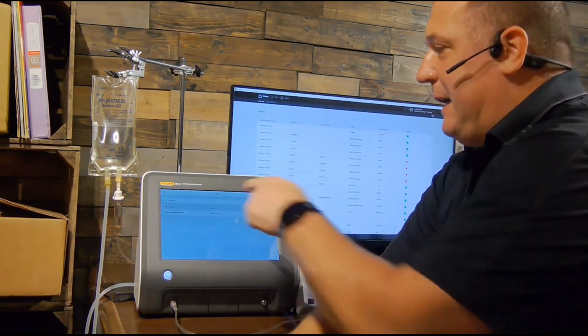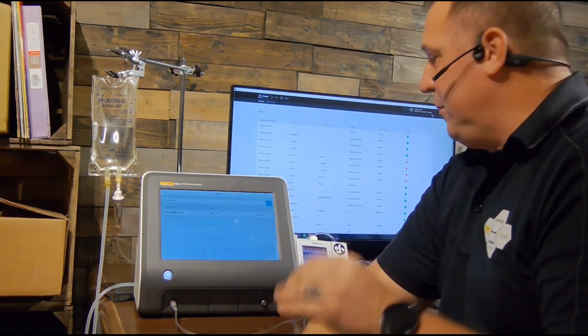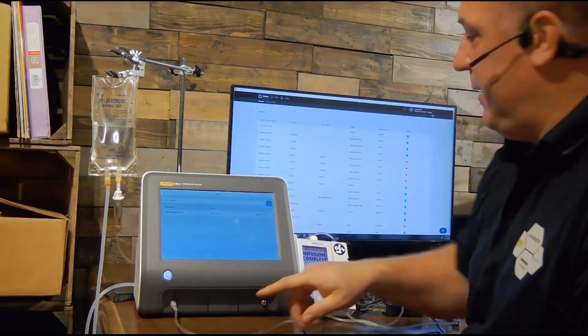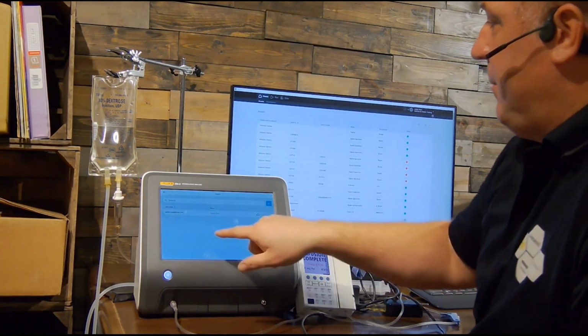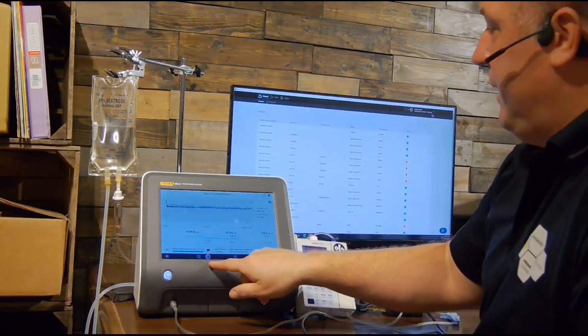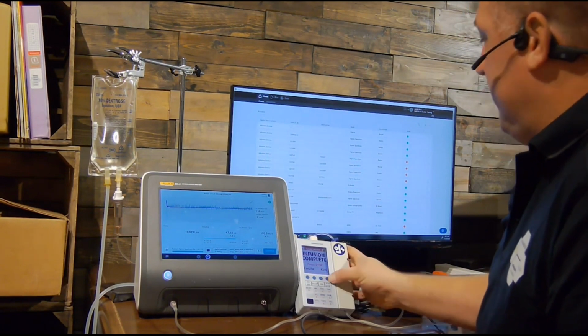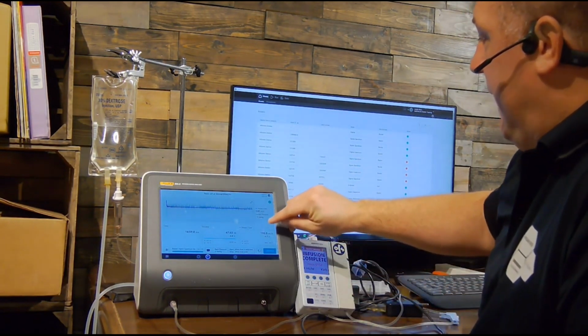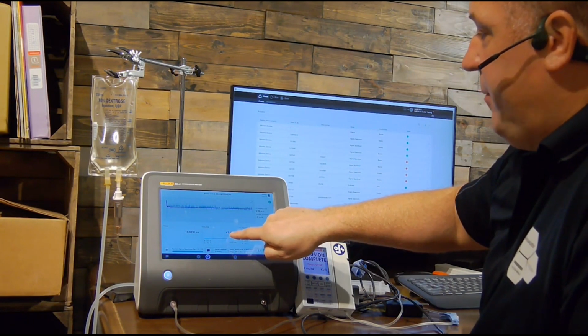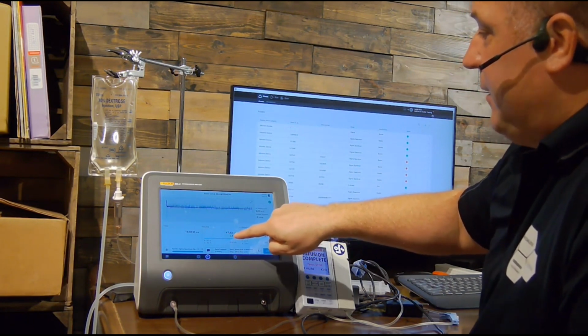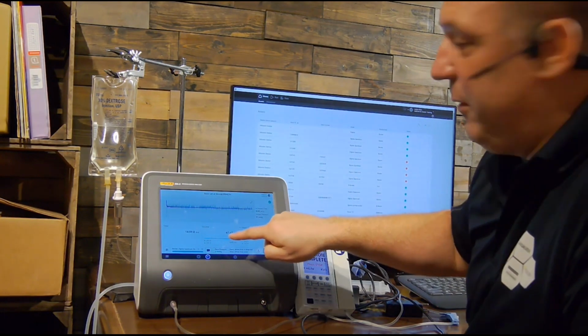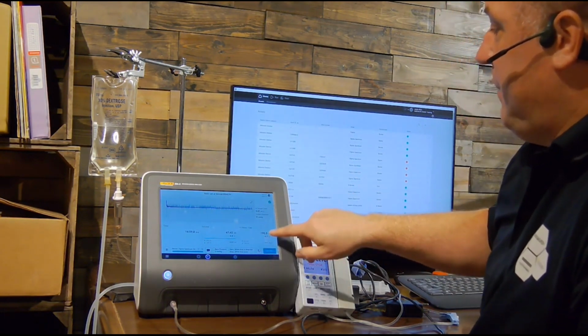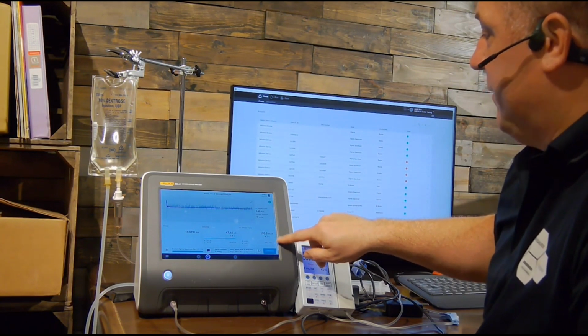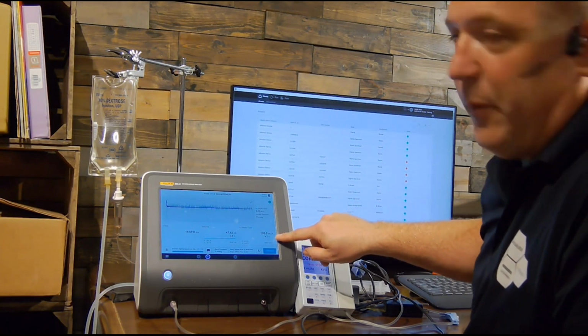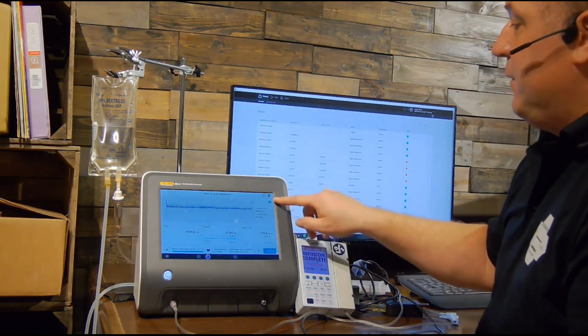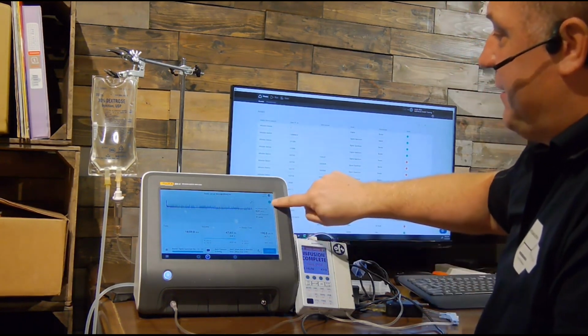If I have OneQA Lite, I'm allowed to have 1 user. If I have the full-blown OneQA, I can have everybody. Oh, my test stopped. So I'm going to pause on users. Let's go back to 1, and I'm going to hit silence on this. And you'll notice now our total volume was 47.62 milliliters. We had 50 set, so that's a negative 4.8% tolerance, which is passing. And my mean flow was 200 milliliters an hour. We were at 190.5 or 4.7% tolerance, and it passed. So this step passed, and I have a green light here.